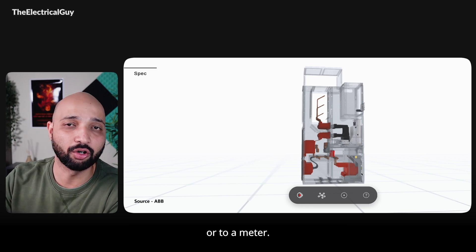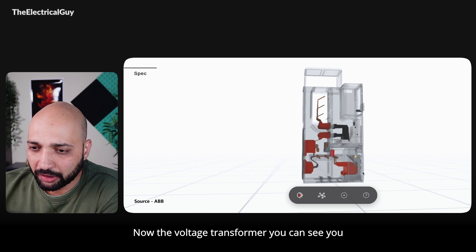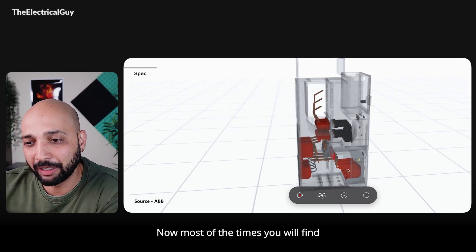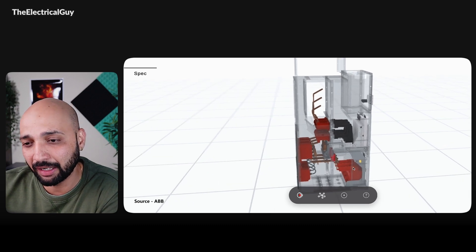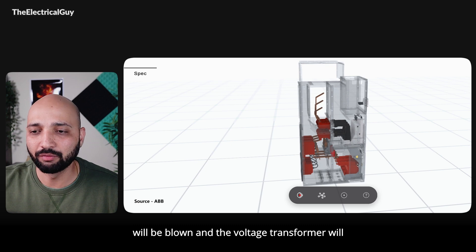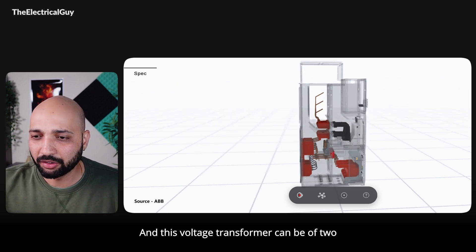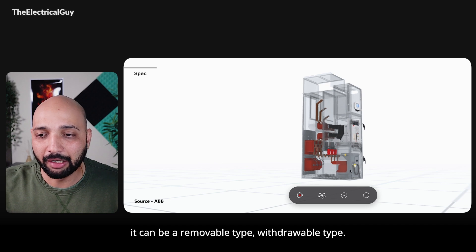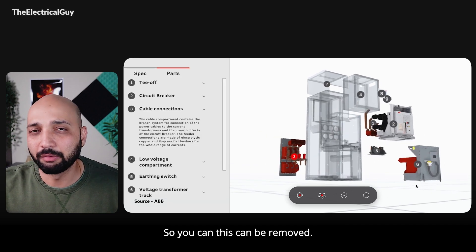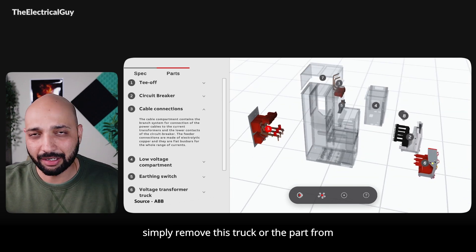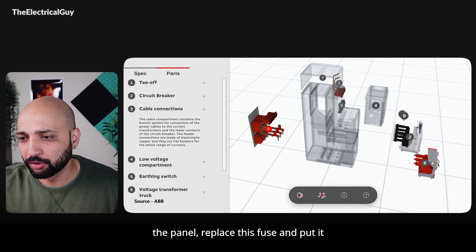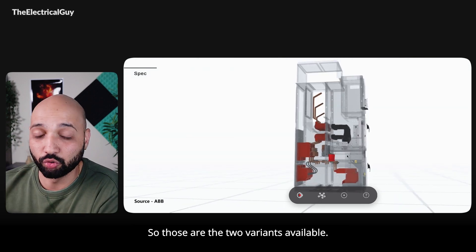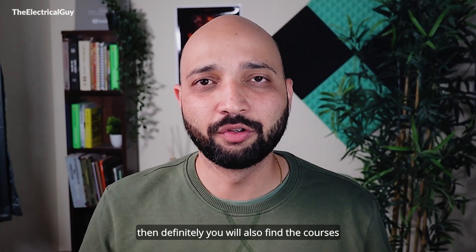This voltage transformer helps us in measuring the voltage, and its input can be given to a relay or a meter. You can also see a rod coming out of it — it's actually a fuse. Most of the time a voltage transformer is connected with a fuse in series, so if something goes wrong the fuse will blow and the VT will be protected. The VT can be either a fixed type or a removable withdrawable type — you can simply remove the truck, replace the fuse, and put it back inside.